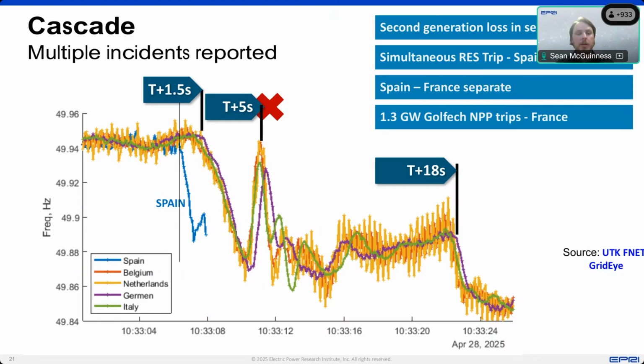Spain. You can see that the frequency began to decline quite substantially, but then the frequency in continental Europe bounced back quite rapidly. So we think that's probably the tripping of the interconnectors between France and Spain, so that when the initial generation was lost in Spain, a lot of power went over reserve from France into Spain. That dragged down the continental European grid frequency. Then as soon as the France to Spain connectors tripped, the frequency recovered.